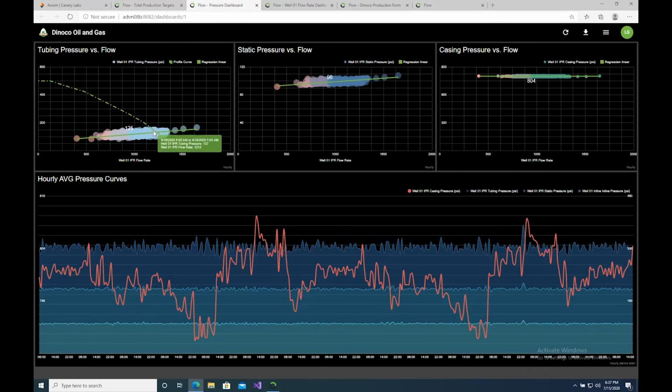It's not too close to the nominal point where I would like to operate. It's actually drifting a little bit away from where I would like to operate this well. So potentially, this is why I'm not getting the flow out of my well. So putting data into context to one another is great to actually go and see where potential problems are. So we should start looking at data in context.